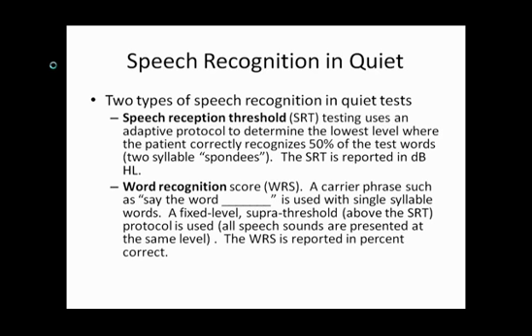An adaptive protocol means the level of each word is changed based on the patient's response. If the patient correctly repeats a word, the next word is presented at a lower level. If the patient incorrectly repeats or doesn't repeat the word, the next presentation level is increased. A pure tone threshold, a speech reception threshold, and a speech recognition in noise threshold all use adaptive protocols.